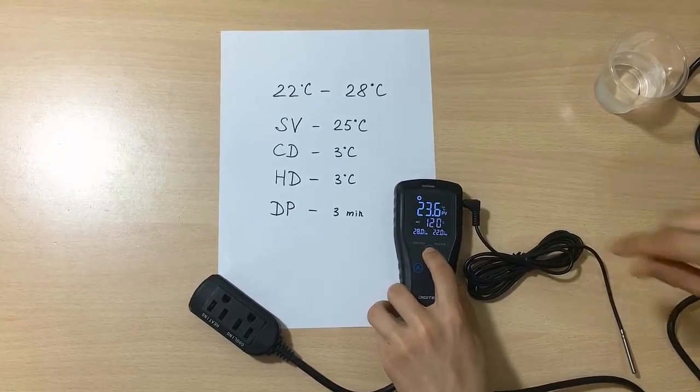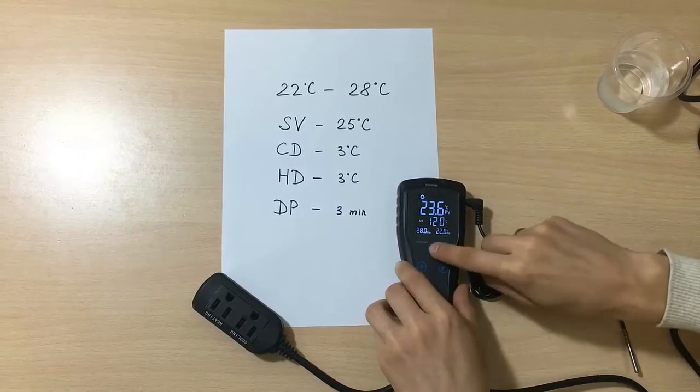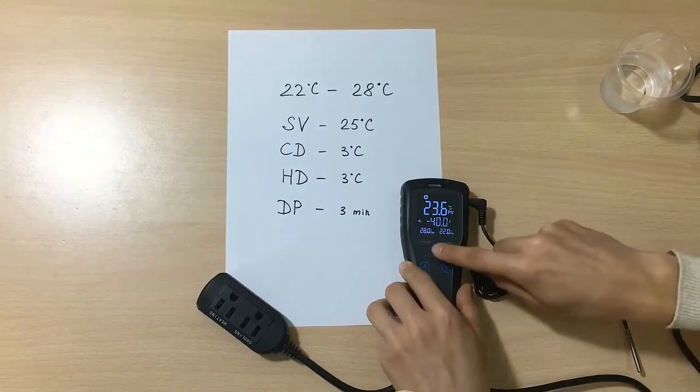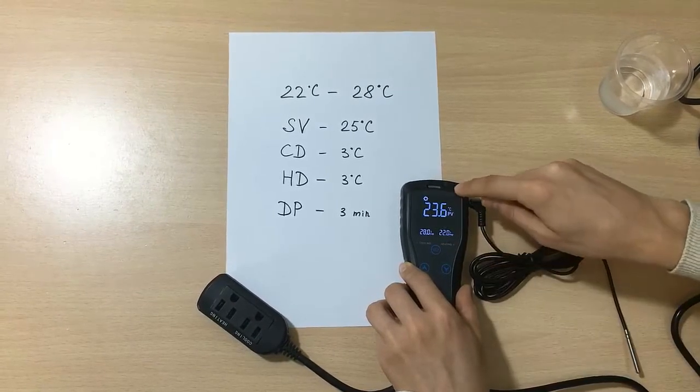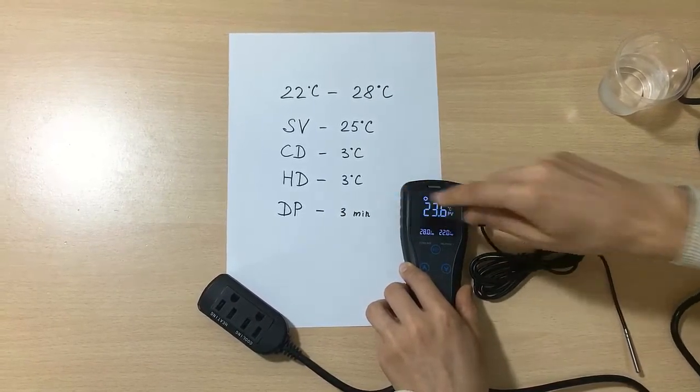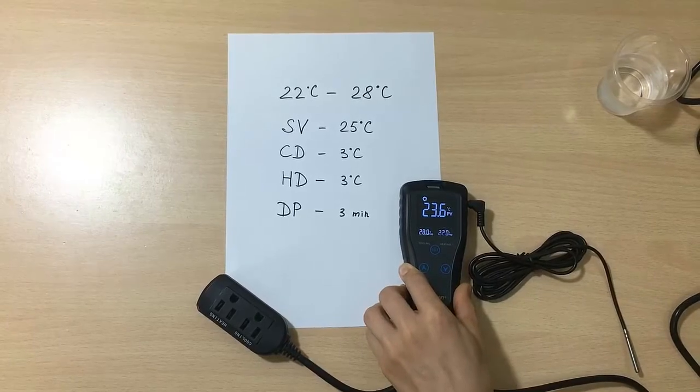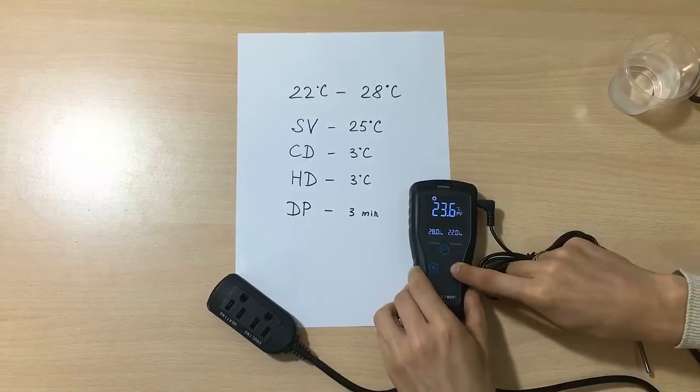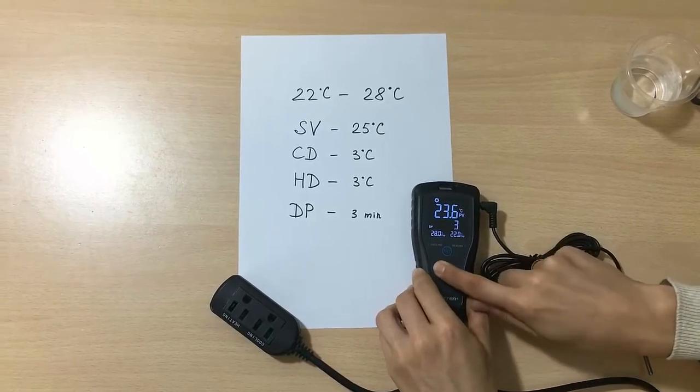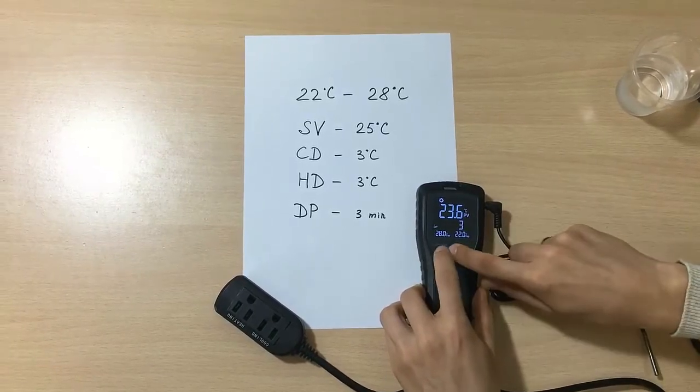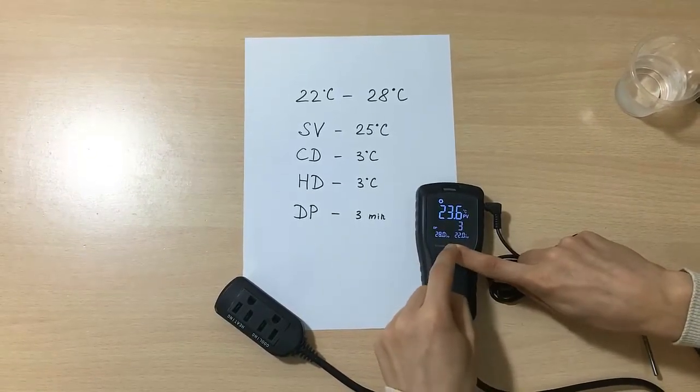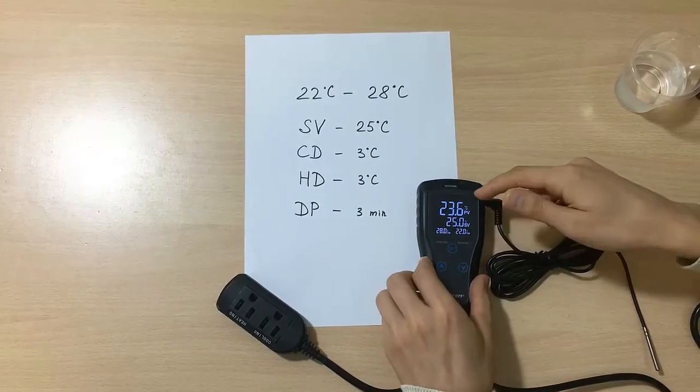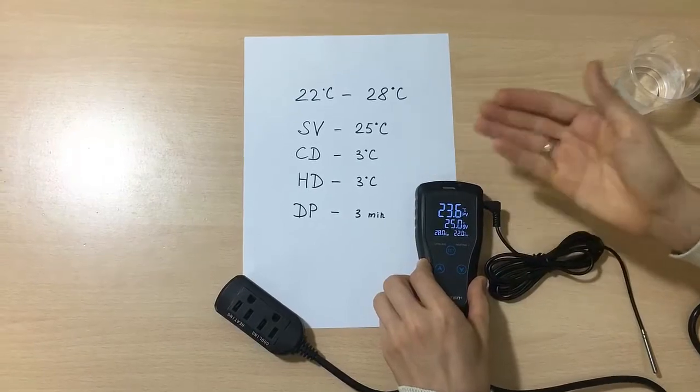AH, as you know, is high temperature alarm. We just don't change anything. As well as AL, the low temperature alarm, we don't change it right now. But now we are interested in DP, which is the time of compressor delay starting. We can change it to any minutes that we want: 2 minutes, 1 minute, 3 minutes, as you wish. And then after this, we have to long press the set button. And now we have the parameters that we need.